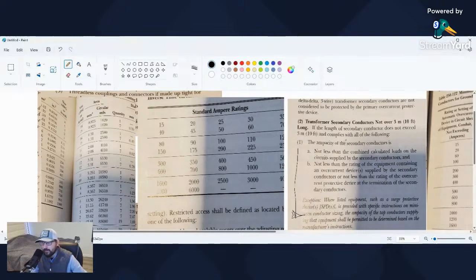every bit of this. Number one, the ampacity of the secondary conductor. So the secondary conductor, I'm going to show you here in a second, would be coming right off of the transformer. You're going to have a primary, which would be 480 volts in. Secondaries would be 240 out. Your secondary conductors, not less than the combined calculated loads on the circuit supplied by the secondary conductors. So you can't be less than the secondary loads, which means you cannot go to the next standard size. If you have 150 amps of wire or 160 amps of wire, you have to go down, being 160, you have to go down to 150 here. If you have 220 amps of wire, you can't go to 225. You have to go down to 200.